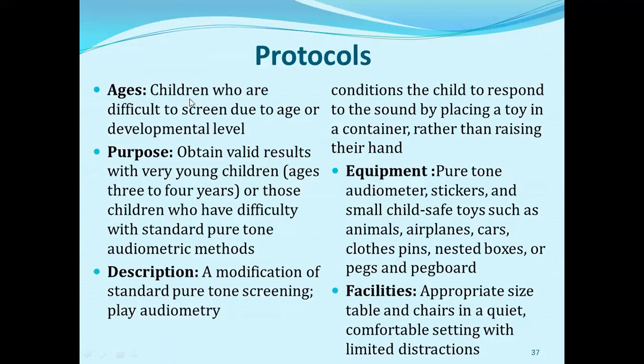Play audiometry protocols are designed for children who are difficult to screen due to age or developmental level. The purpose is to obtain valid results with young children aged 3 to 4 years and those who have difficulty with standard pure tone audiometric methods. The child is conditioned to respond to sound by placing a toy in a container rather than raising their hand. Equipment needed includes a pure tone audiometer, stickers, small child-safe toys such as animals, airplanes, and cars, clothespins, and nested boxes or peg boards. An appropriately sized table and chair with limited distractions are required.